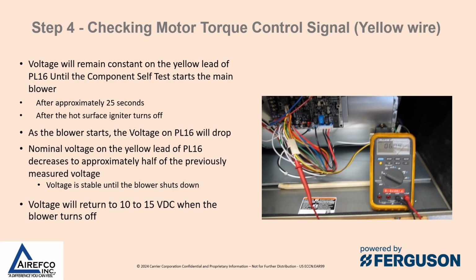So the voltage will remain constant on the yellow lead of PL16 until the component self-test starts the main blower. After approximately 25 seconds and after the hot surface igniter turns off, the blower will start and the voltage on PL16 will start dropping. Nominal voltage on the yellow lead of PL16 decreases to approximately half of the previous measured voltage. Voltage is stable until the blower shuts down. Voltage will return to 10 to 15 volts DC when the blower shuts off.